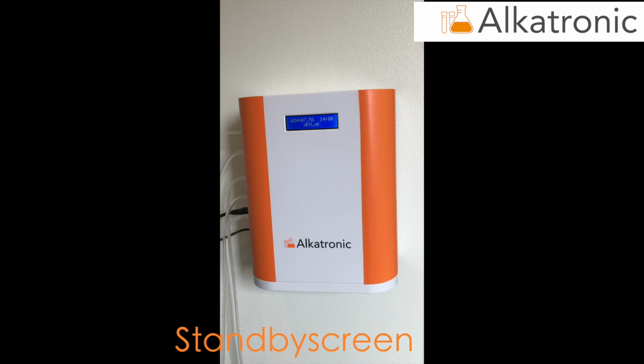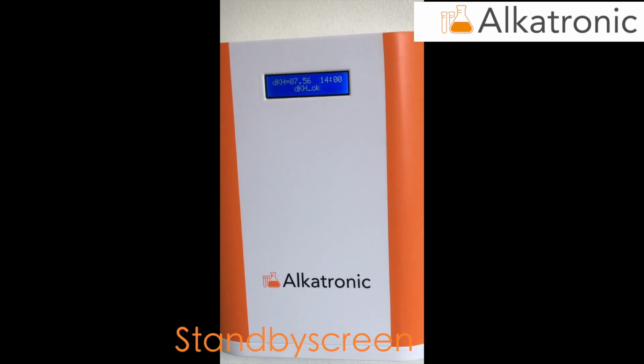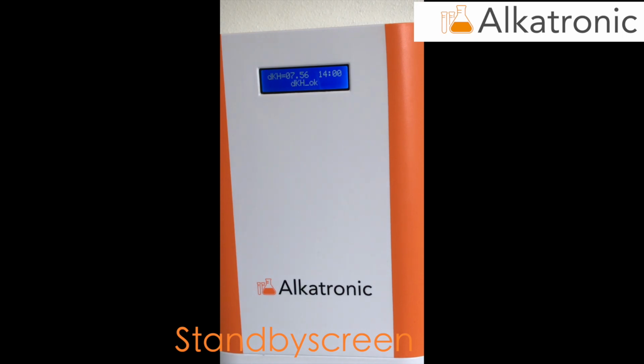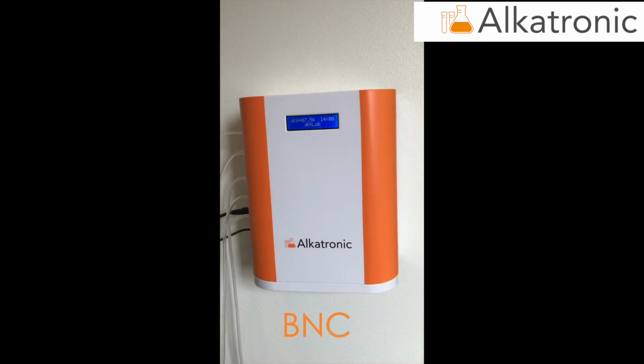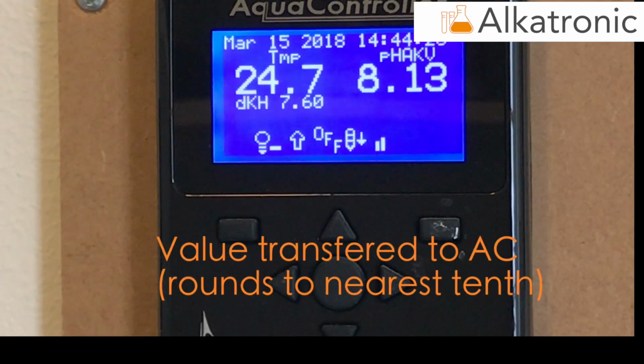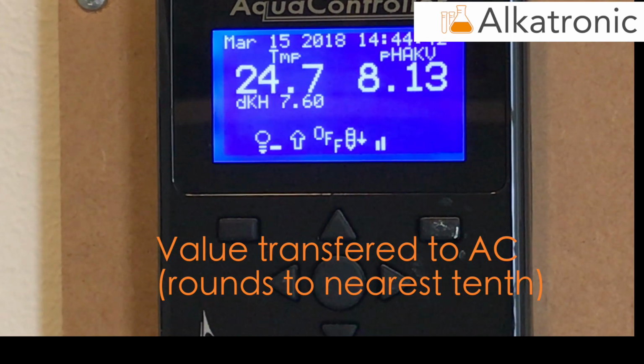Now the machine is ready, and you have the new DKH measure ready. You can see it, 7.56, and the next measure will be taken at 2 p.m., and the DKH is okay because it is within my set reference intervals. Also have a look, I have a BNC connection, as you see. And immediately the new value is transferred to the aquarium computer, and it says exactly 7.60. That is deliberately rounded up because we round to the next tenth for the third-party aquarium computer. The value was 7.56, and that is correctly transferred to the aquarium computer here as 7.60.